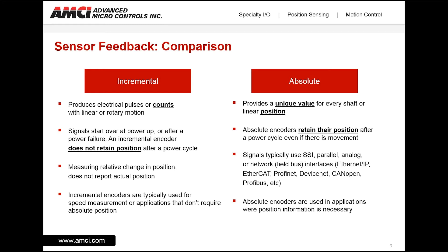Absolute position feedback, on the other hand, provides a unique value for every shaft or linear position. Absolute encoders retain their position after a power cycle, even if there is movement. Absolute encoder signals come in many forms, but those we typically see today are SSI — synchronous serial interface — analog, or the up-and-coming network interfaces such as Ethernet IP, EtherCAT, or PROFINET. Absolute encoders are used in applications where position information is necessary.